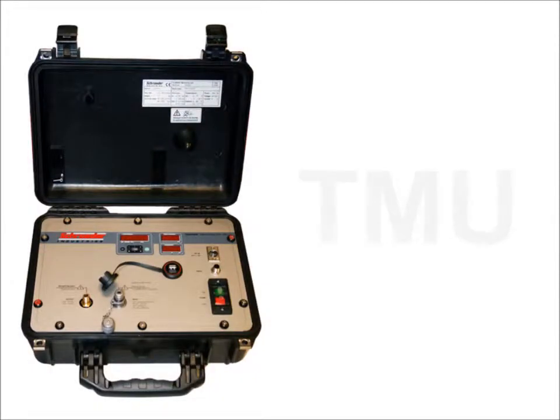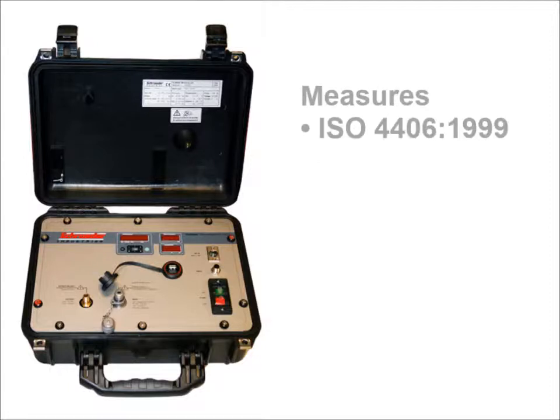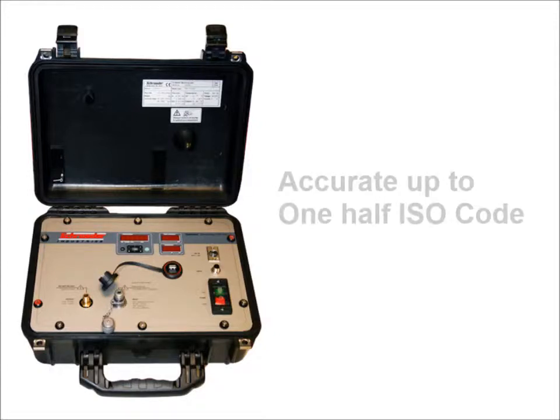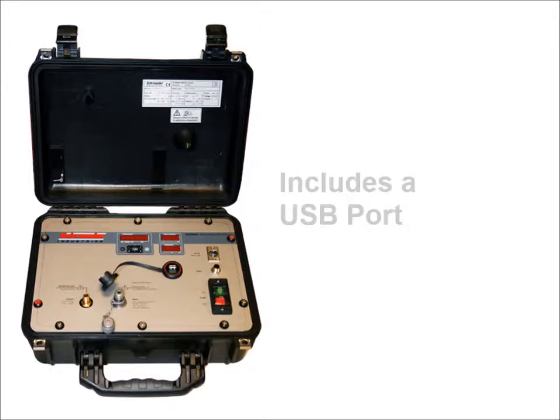It's powered by a 24 volt DC power supply which comes with the unit. The unit is capable of measuring the ISO codes, SAE codes, or the NASA codes, also called NAS codes. The measurement accuracy is plus or minus one half ISO code. The unit also has the capabilities of downloading the information through a USB port to your computer.